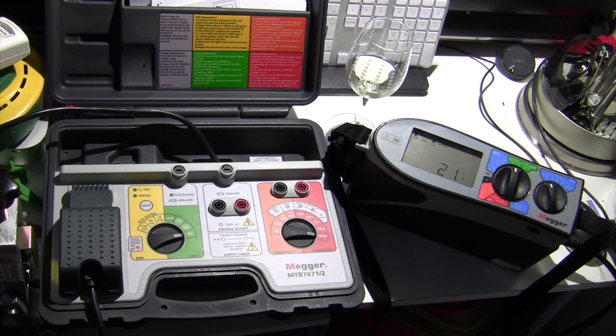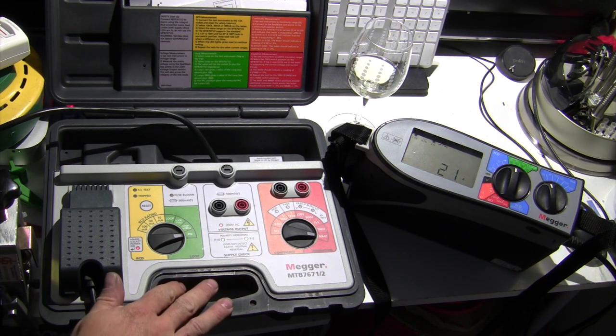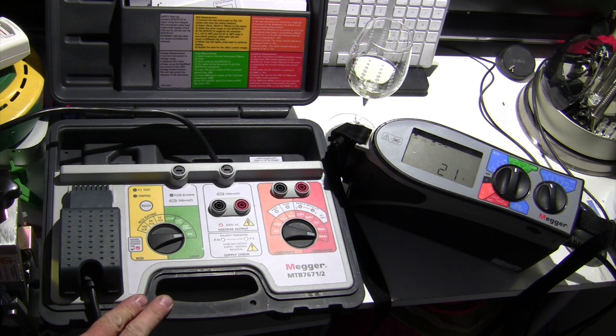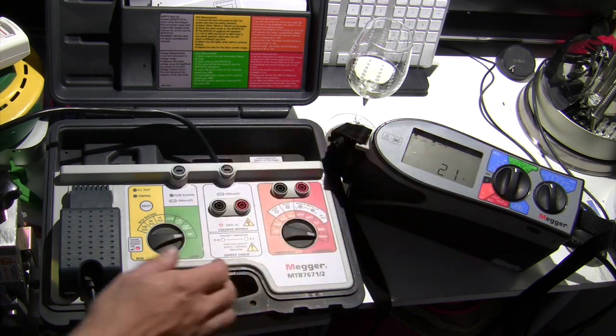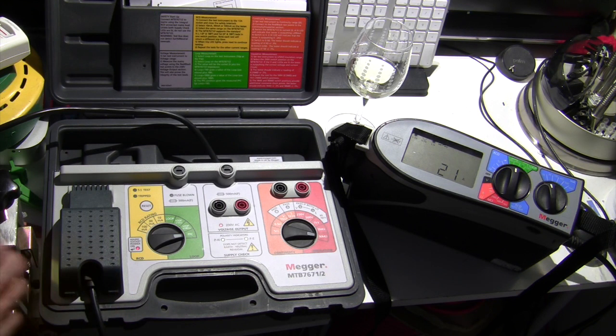So that's the full gamut of tests that we can do with this thing. And obviously that takes us through most of the functions of what is a fairly basic tester here. Obviously other testers have far more functionality, things that we don't have here, like for example phase rotation or something like that. But all we're concerned about here are the basic tests, and that's good enough for monthly checks, annual calibration, and they'll test the full range of whatever test you present to them, or at least that's the idea.